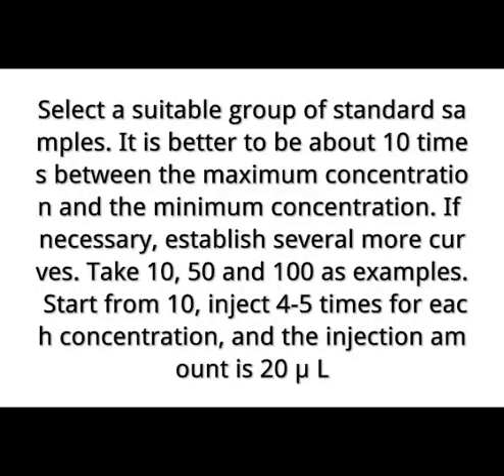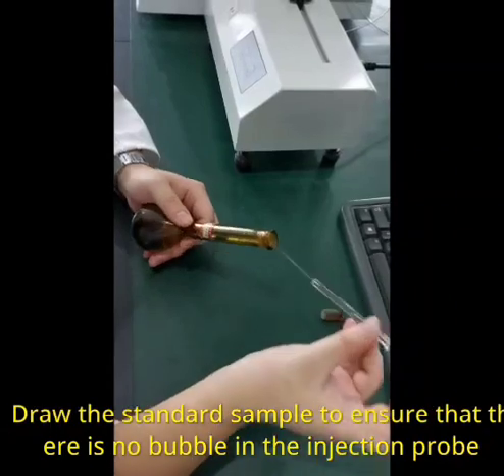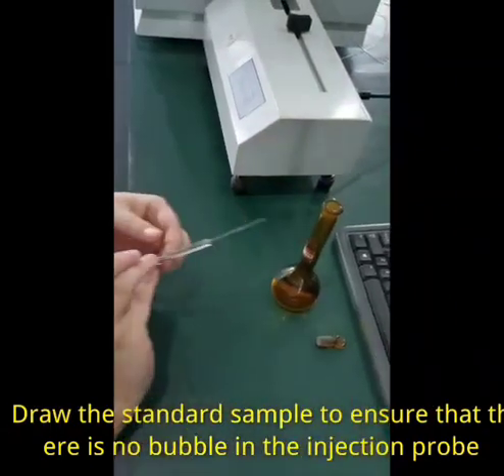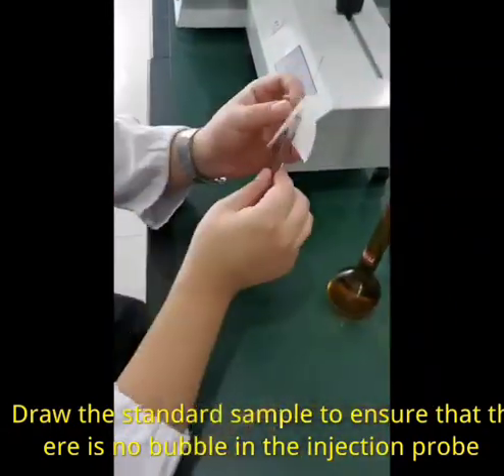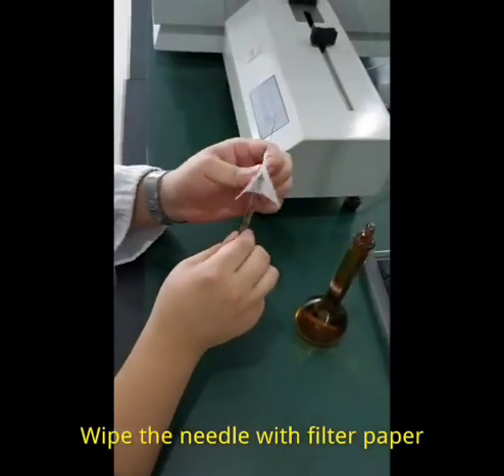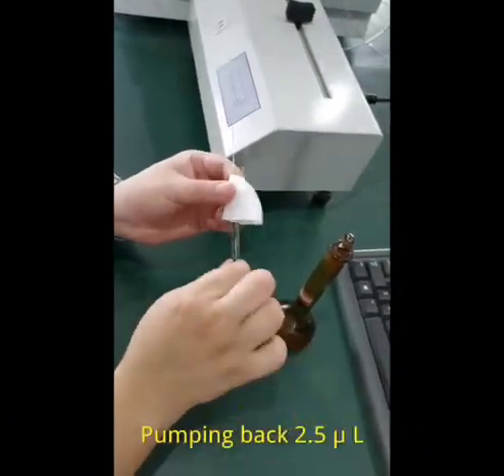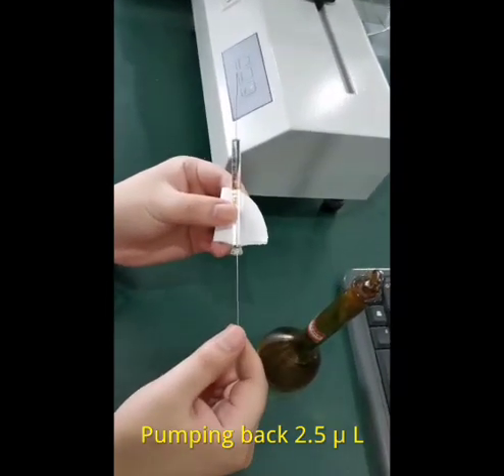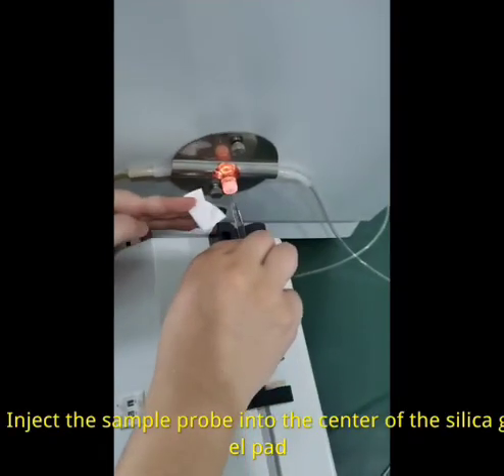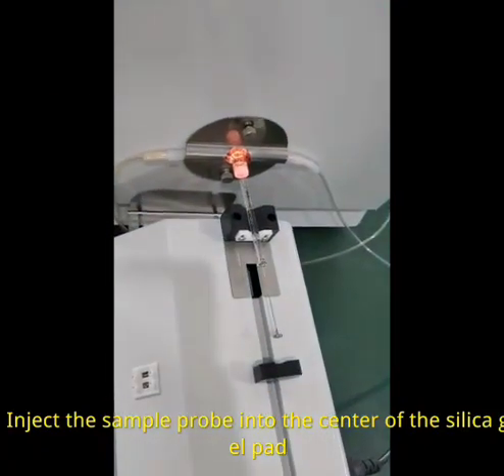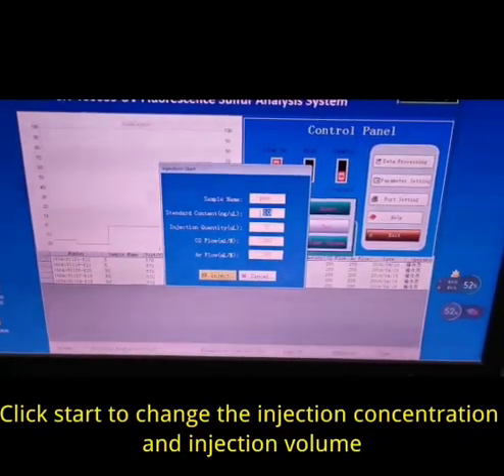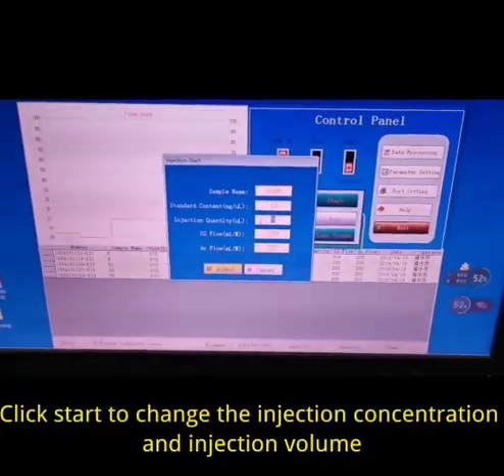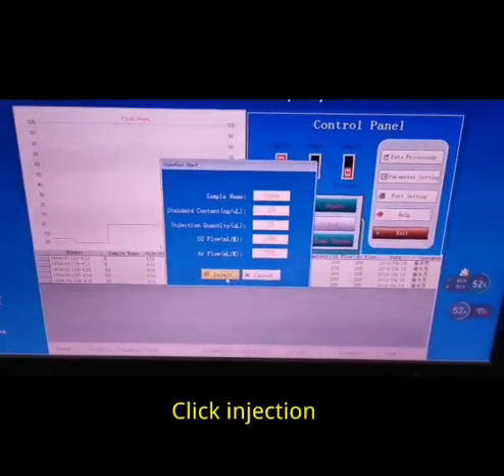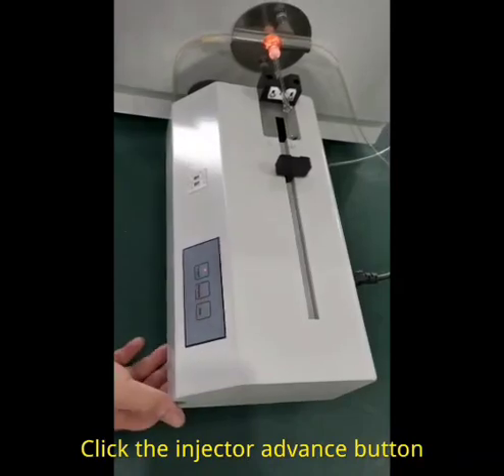Start from 10, inject 4 to 5 times for each concentration, and the injection amount is 20 μL. Draw the standard sample to ensure that there is no bubble in the injection probe. Wipe the needle with filter paper. Pumping back 2.5 μL. Inject the sample probe into the center of the silica gel pad. Click Start to change the injection concentration and injection volume. Click Injection. Click the Injector Advance button.